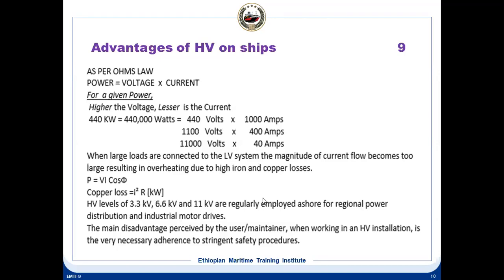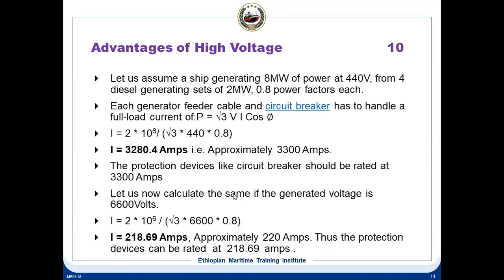Okay, so this is a basic concept. You are increasing the voltage, so the current is reduced. In the coming topics, we will see how it is going on. Here there are a few examples I have given. Now, let's assume a ship generating 8 megawatt of power at 440 volt from 4 diesel generator sets of 2 megawatt, 0.8 power factor each. Each generator, feeder cable and circuit breaker has to handle the full load current. So the cable connected from the generator and the circuit breaker in the circuit, all have to cater for a very high current.